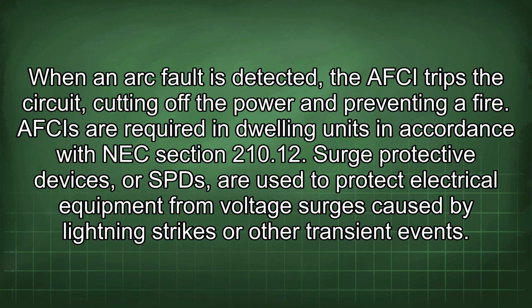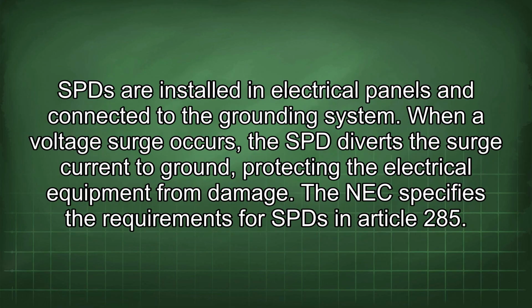Surge protective devices, or SPDs, are used to protect electrical equipment from voltage surges caused by lightning strikes or other transient events. SPDs are installed in electrical panels and connected to the grounding system. When a voltage surge occurs, the SPD diverts the surge current to ground, protecting the electrical equipment from damage. The NEC specifies the requirements for SPDs in Article 285.